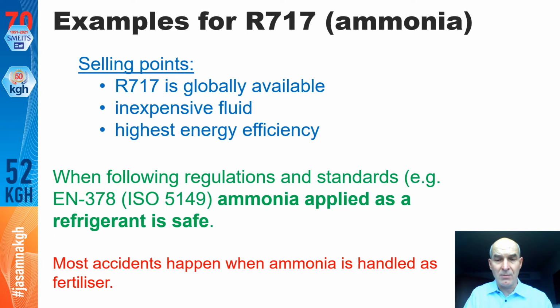So why is ammonia such a good fluid? Because it's globally available, very inexpensive, and has one of the highest energy efficiencies when it comes to this kind of chiller application. When you follow the regulation and standards, for example EN 378, ammonia applied as a refrigerant is very safe. Most accidents actually happen when it's handled as a fertilizer.